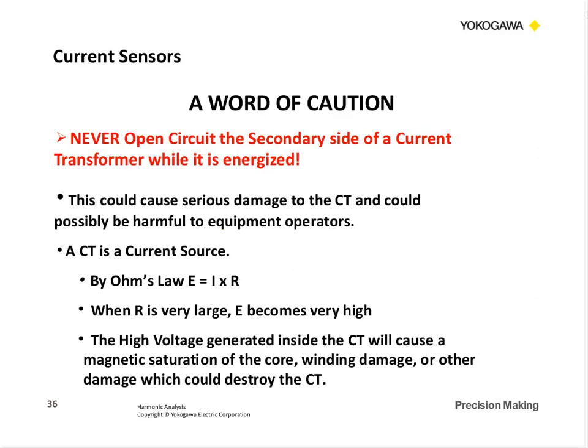Here's a word of caution. Never open circuit the secondary side of a current transformer while it's energized. A CT is a current source. So by Ohm's law, E equals IR. This is internally. What happens when R goes very large, or if we open circuit it? E becomes very high, and this is the internal voltage that's generated inside that CT. With that high voltage generated inside, it can cause magnetic saturation of the core, actually burn the windings, damage it, could just totally destroy the CT. So it's a very dangerous situation. So always de-energize the current going through the CT before you disconnect it.